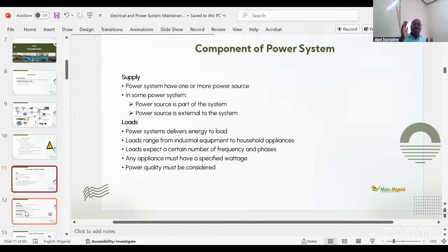When you are able to manage these parameters well, your equipment will last - the lifespan of your equipment will increase, you reduce cost, and you minimize risk. If the voltage you are bringing is like 250, 260 single phase, and you allow this voltage to go into your facility, they will call you from home that your building is on fire because that voltage is too high. So you have to monitor the voltage value, the frequency, the power.